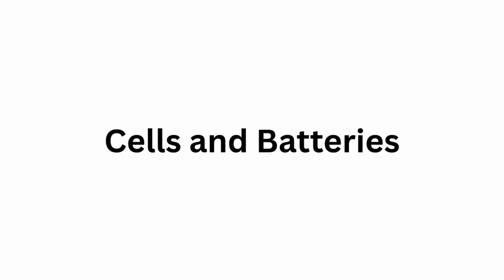The most common one people probably recognize is the ampere hour, Ah rating. What exactly does that tell us? The Ah rating is a measure of total energy capacity. It's basically current multiplied by time. So if a battery says, for example, 48Ah at an 8-hour rate. The rate matters. Hugely. It means it can deliver 6 amps, that's 48 divided by 8, continuously for 8 hours before its voltage drops below a certain point, usually around 91% of its nominal voltage. If you draw current faster, the total Ah capacity you get will be lower.